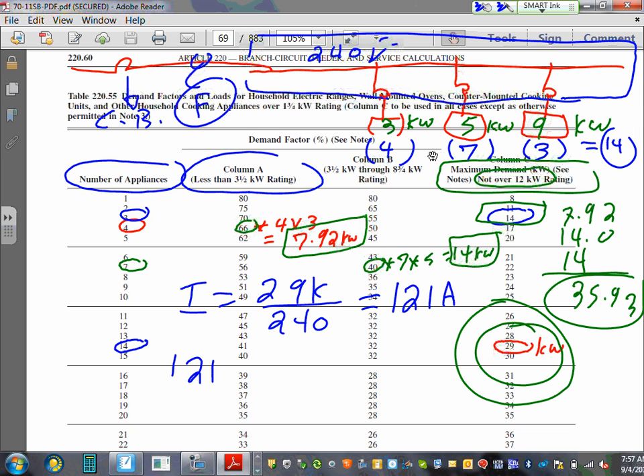So 121 amp. Take it to the table that we use to size the service or the feeder, which is 220. Okay, 310.15(B)(7). It's on page 153. So I have 121. My next standard is 125, right? Can you guys see that? So this is 125 amp. So my circuit breaker here is 125 amp. Did you guys see that? My circuit breaker is 125 amp.